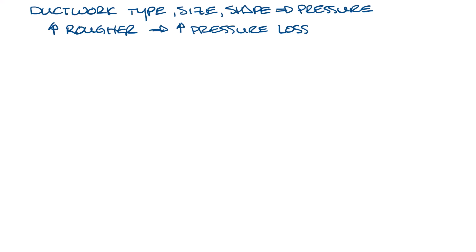As far as shape goes, round ductwork will have less pressure loss than rectangular ductwork because there's less surface area exposed to the airflow. For instance, if we had a 12 inch round duct, it'll have an area of pi times r squared, and so that is pi times 6 squared, which is 113 square inches.